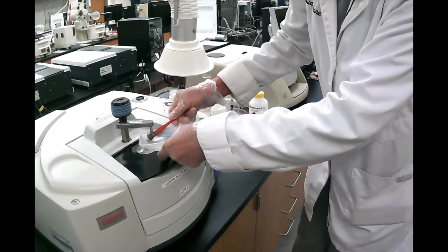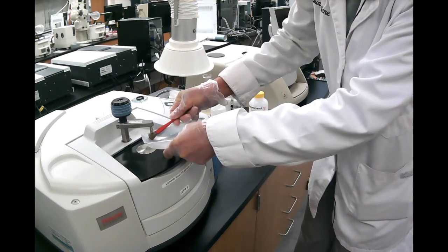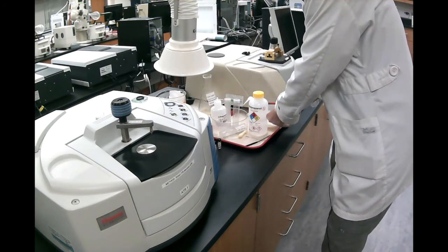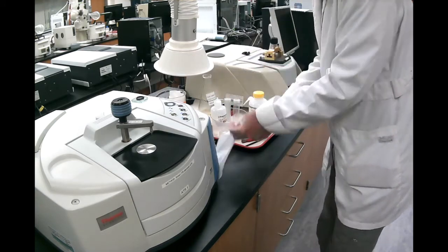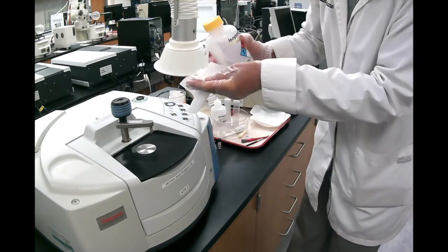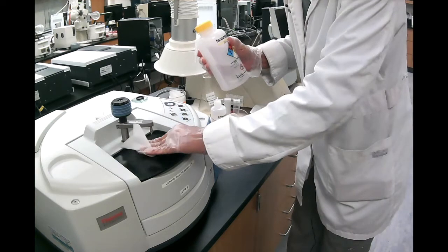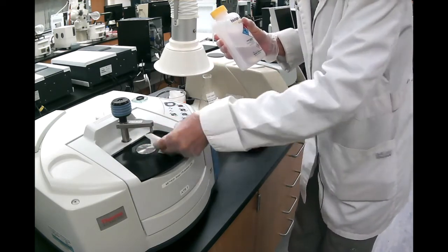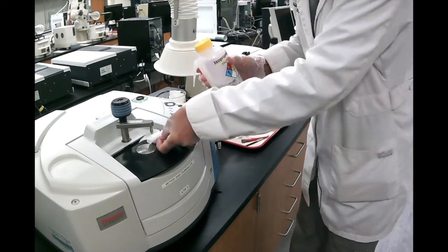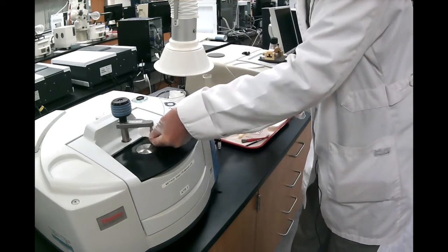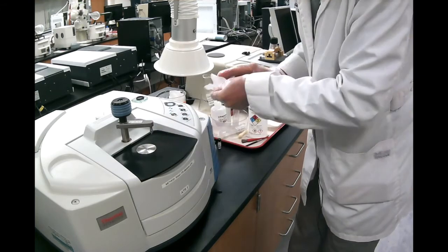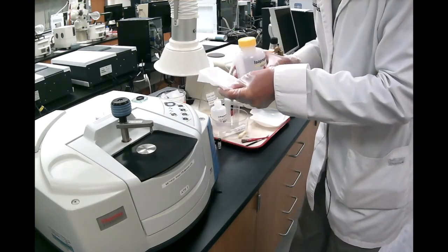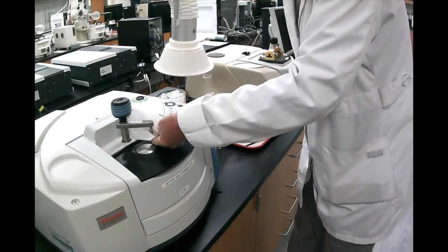I can also brush a little bit the tip of this cone. And then once you brush it, you just need to clean it up with some isopropanol. Both of them. Clean the surface of the crystal as well as you can. And then I'm going to clean the tip of this cone on the arm there. You do it twice and you're good to go.